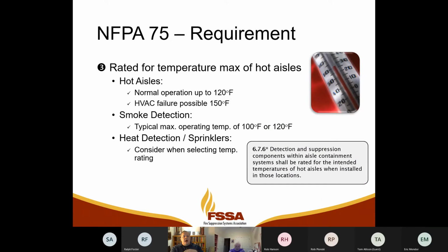The third thing: equipment should be rated for the temperature maximum of the hot aisles. The HVAC engineer is going to have to help define what that maximum temp could be, and a lot of that depends on the inlet temperature to the servers. How cold are they running the room? Hot aisles normally can have temperatures approach 120 degrees. If the HVAC fails, the heat coming off the servers, those hot aisles can quickly reach 150 degrees Fahrenheit.